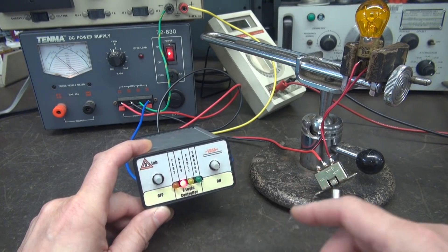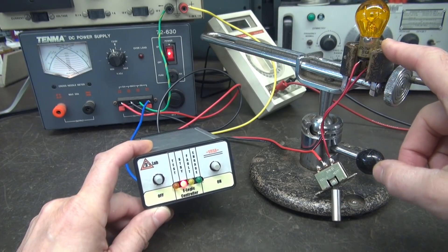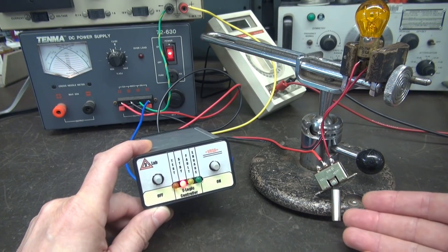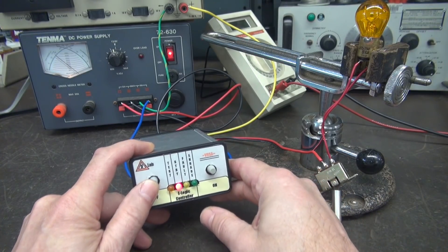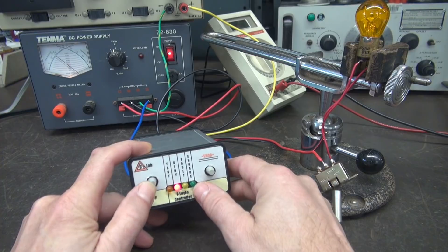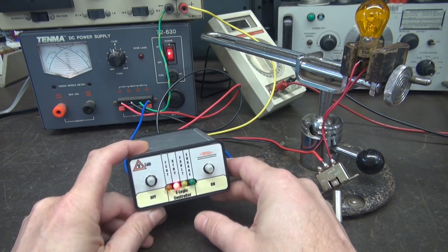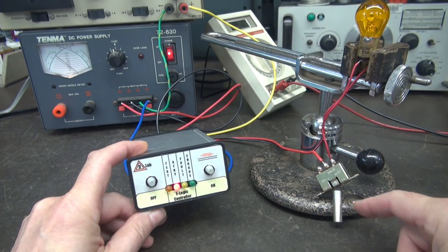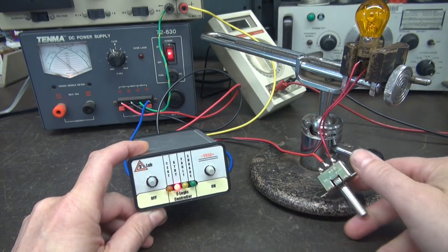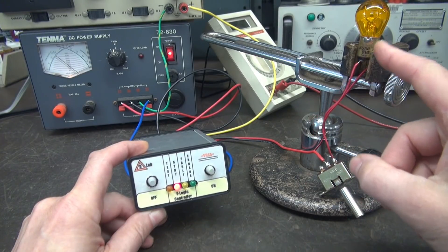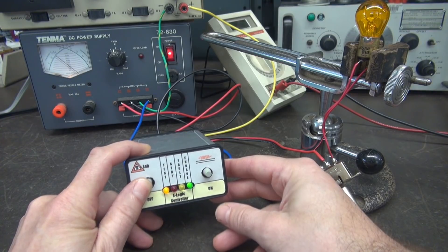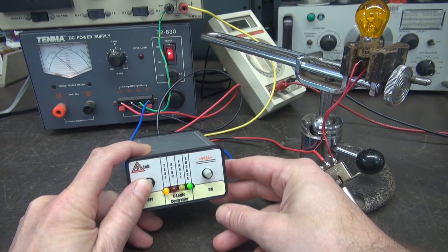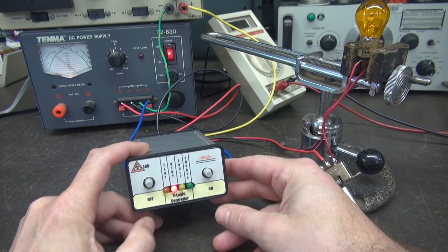Let's pretend that this light bulb is a contactor on your machine that's running a process. The first thing that Versa does for you: if you hit the off button, it goes into test mode and it's looking out there to see if it sees the load. So I put a switch here. If I open up the line now going to the contactor and I hit Versa, you'll see you have a fault indication. Those two lights say, hey, something is wrong.